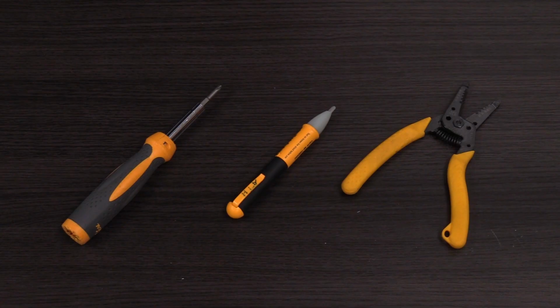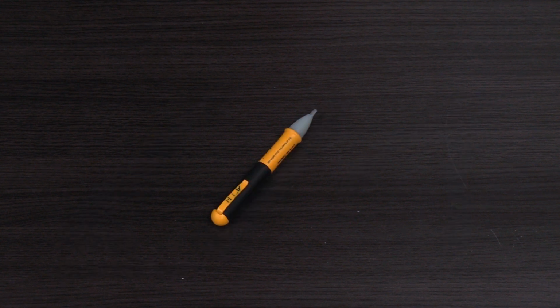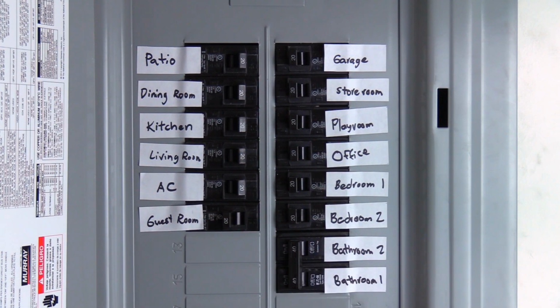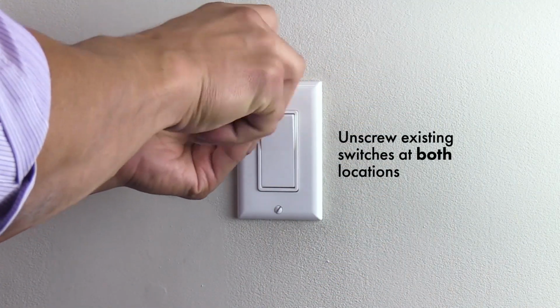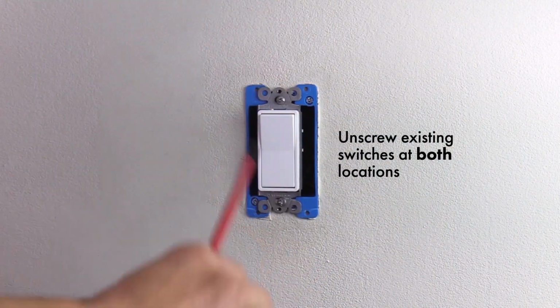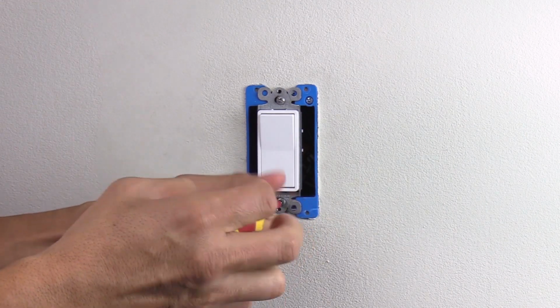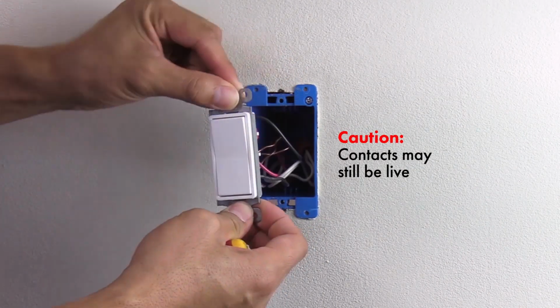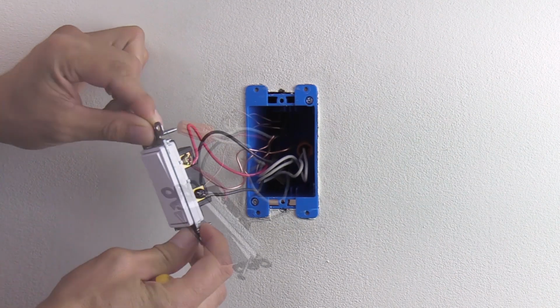For this installation, you will need the following tools: a Phillips screwdriver, a voltmeter, and wire strippers. Turn the power off from the circuit breaker for the switches to be replaced. Unscrew the existing light switches at both switch locations. Carefully pull the switches out of the wall as the contacts may still be live.